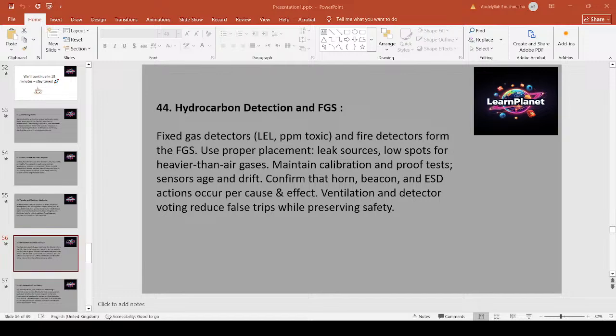Fixed gas detectors and fire detectors must be placed at likely leak points, low spots for heavy gases, and near possible ignition sources. Implement voting and delay logic to reduce false trips while ensuring safety. Critical detection triggers ESD and alarms. Maintain calibration and proof testing schedules; gas sensors age and drift. Verify full cause and effect, that horn, beacon, and ESD actions occur as promised during proof test. Example: place LEL sensors near pump seals and around the vapor recovery system and tie them into the FGS logic with 2 out of 3 voting for robustness.